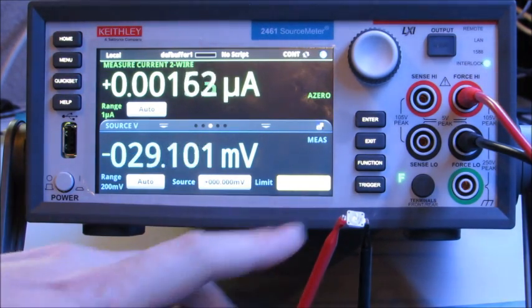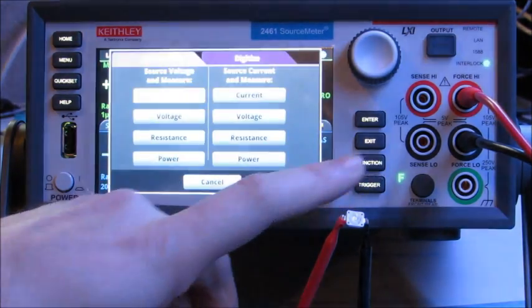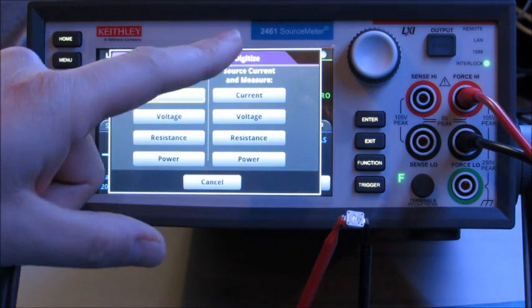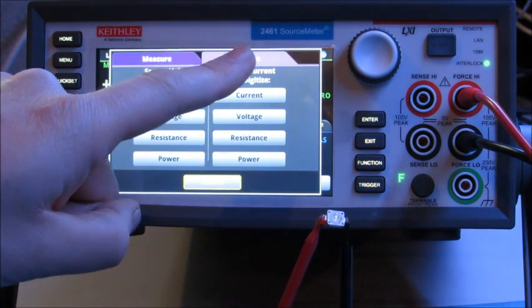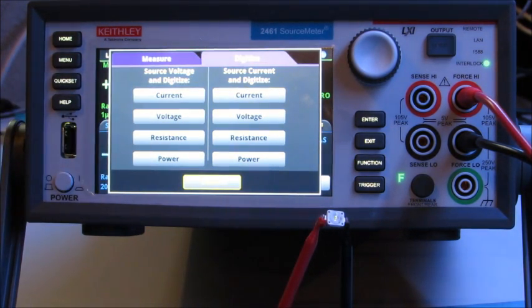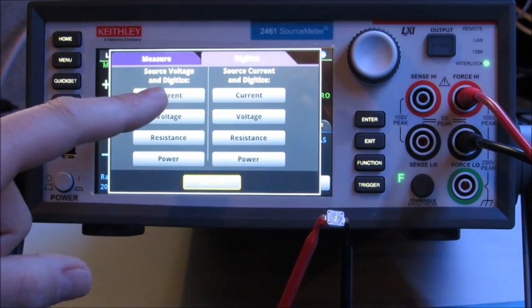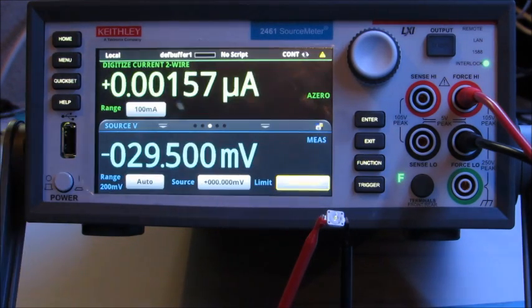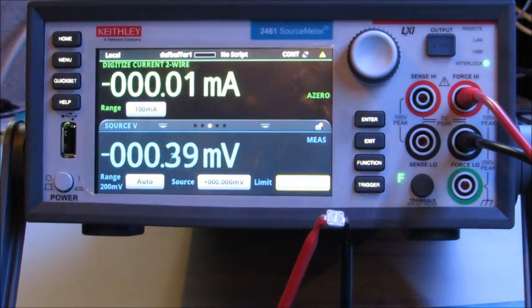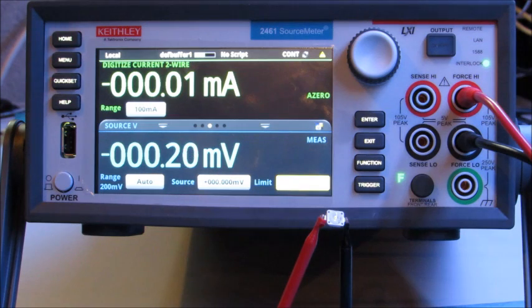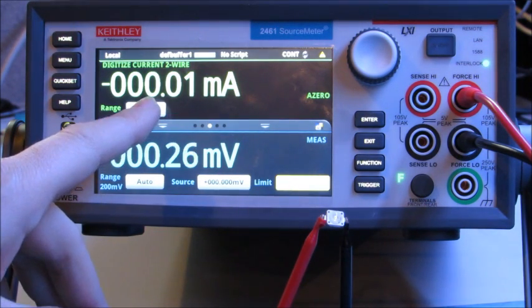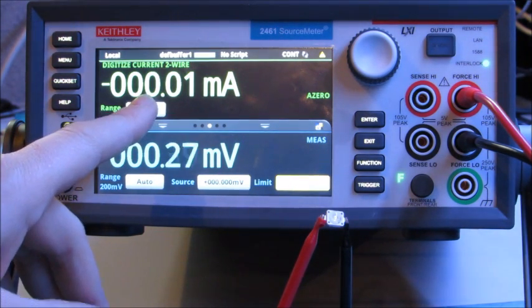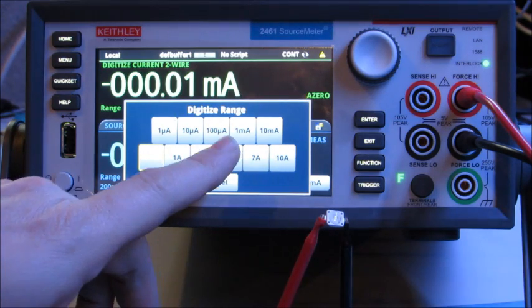First thing I need to do is hit function and I need to hit the digitize tab and I'm going to source voltage and digitize current. Now to ensure that I get the right measurements, I'm going to change the measure range from 100 milliamps to 5 amps first.